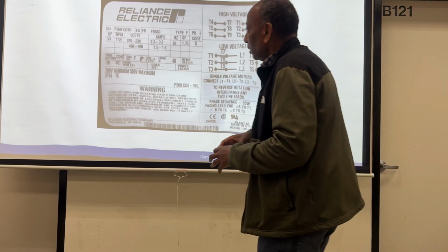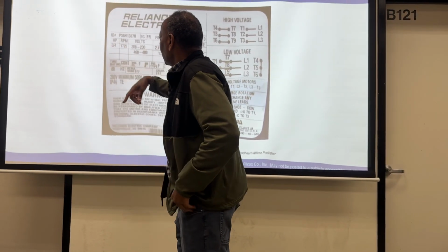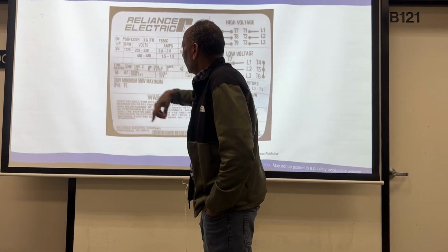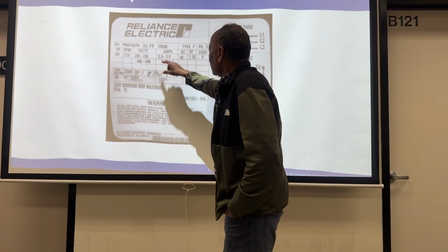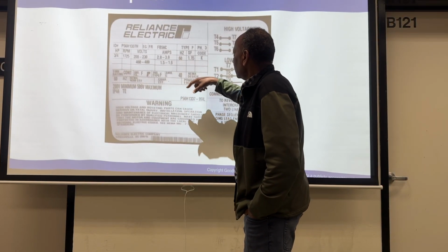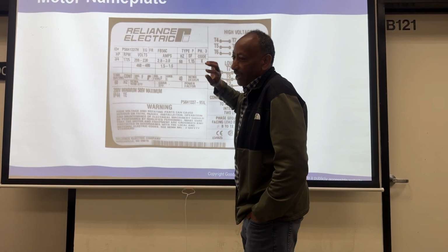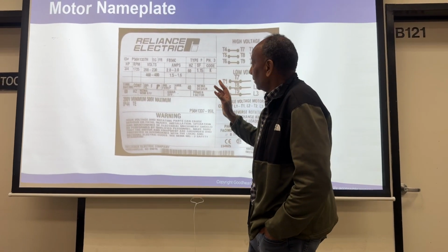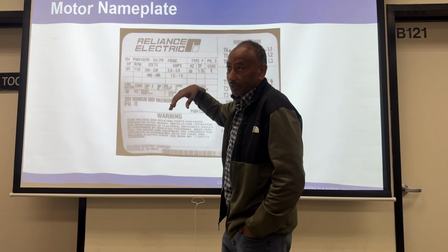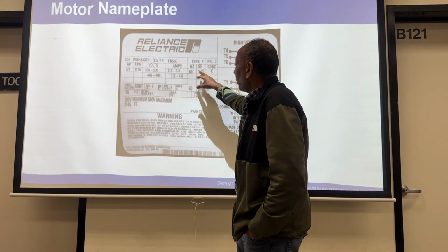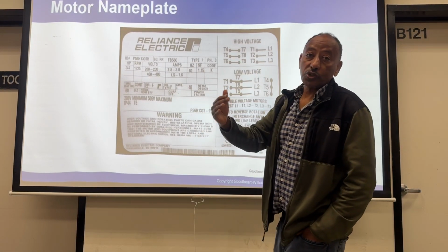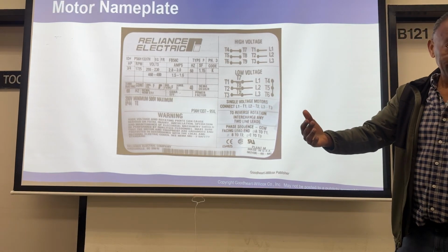It tells you what horsepower it is, what RPM it goes, the voltage it's taking, the amperage it's taking, at 60 hertz. This is called the service factor. Service factor means, let's say the amperage is 2.8, you multiply it by 1.15, so for a short time it can take as much as that.